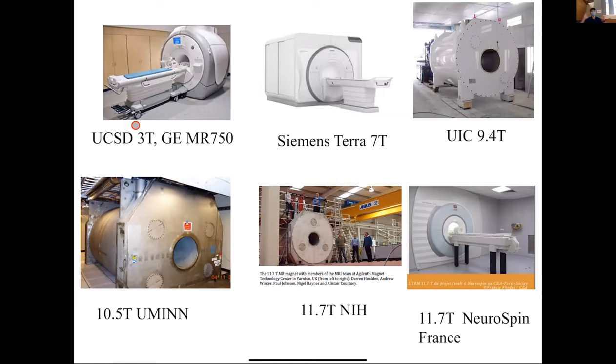Siting can be expensive too — you might spend two to three million dollars on the magnet and then another million to build the room. Seven Tesla is where the field is heading clinically. On the research side there are even higher field systems: 9.4 T, 10.5 T, and 11.7 T. The 11.7 T magnet just opened in France from the NeuroSpin consortium.